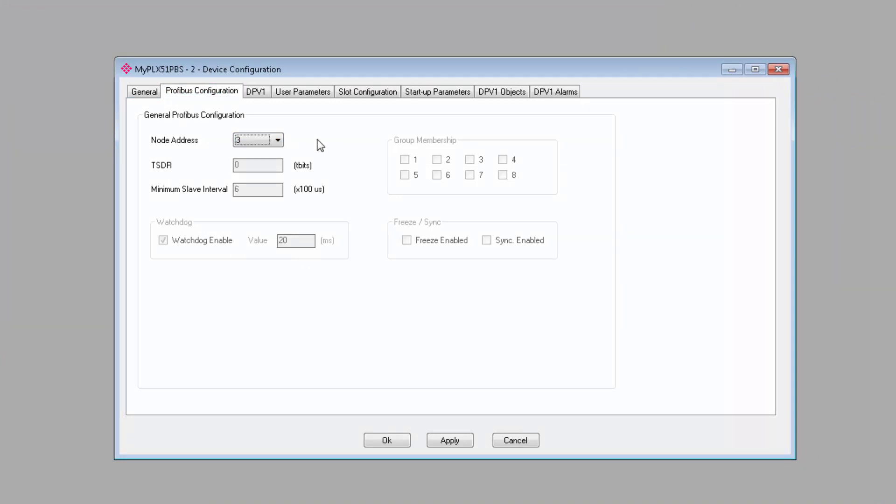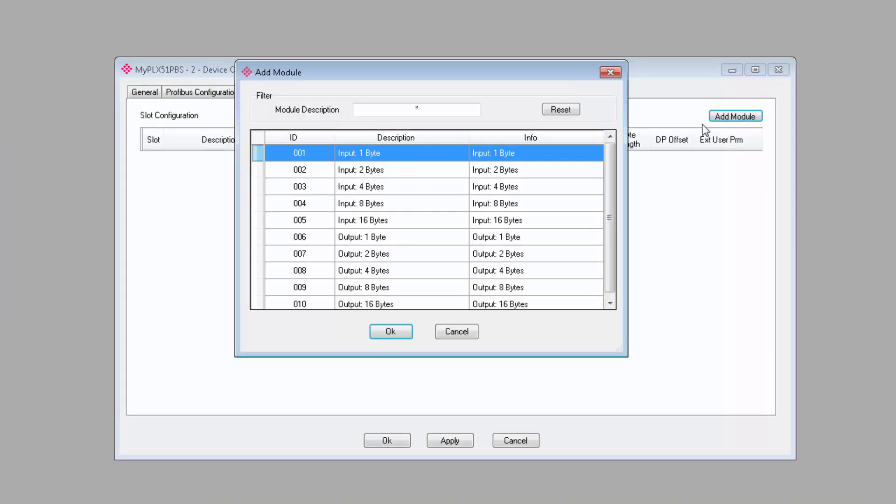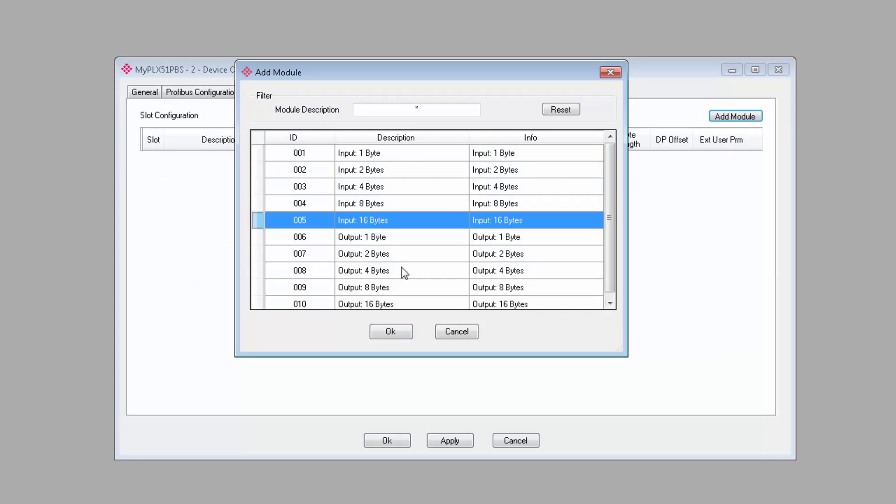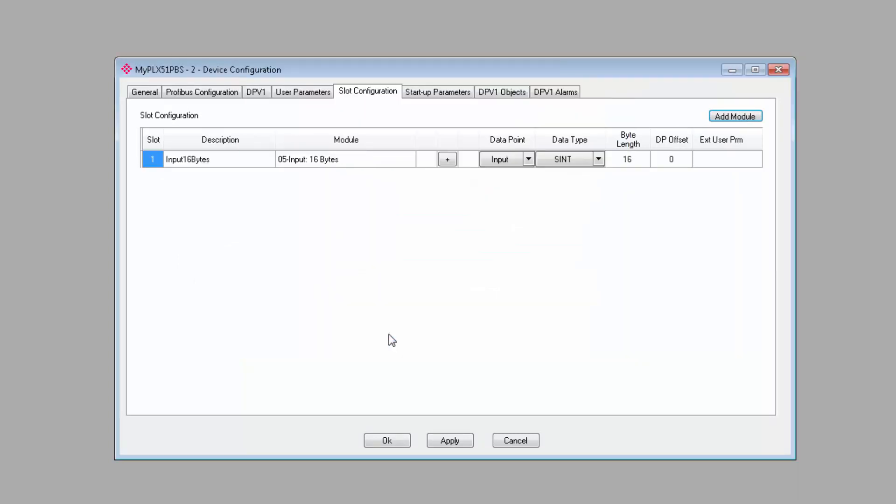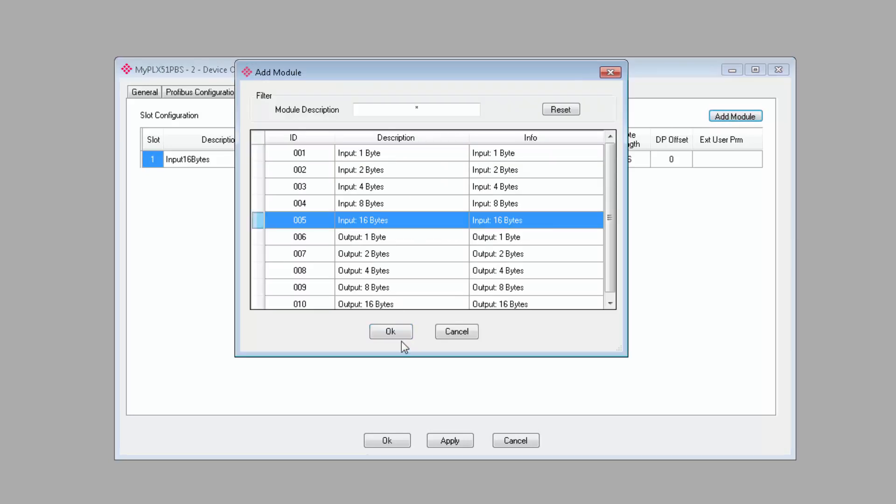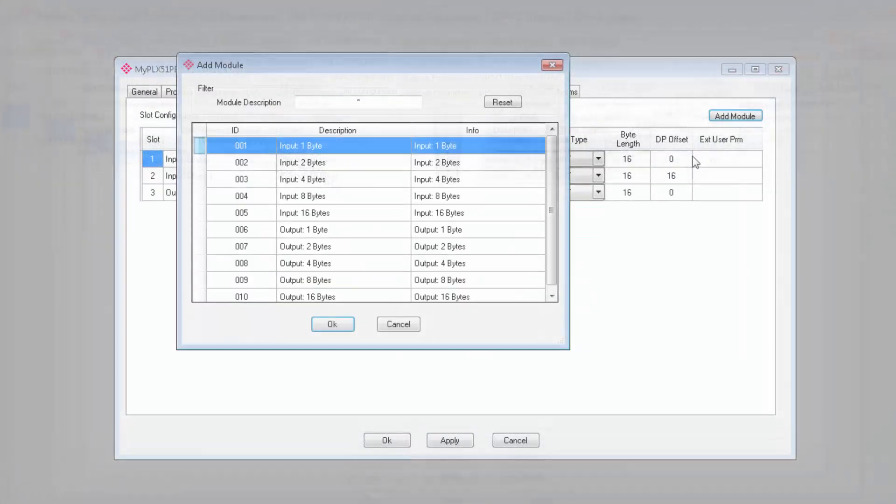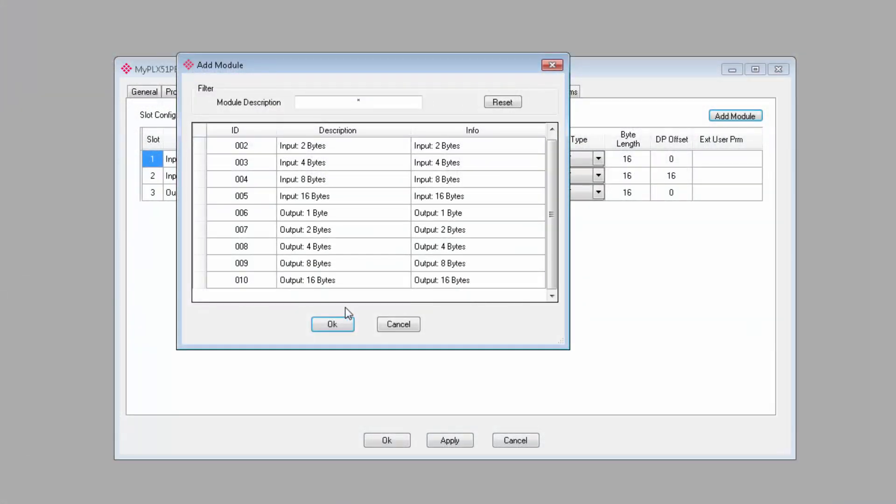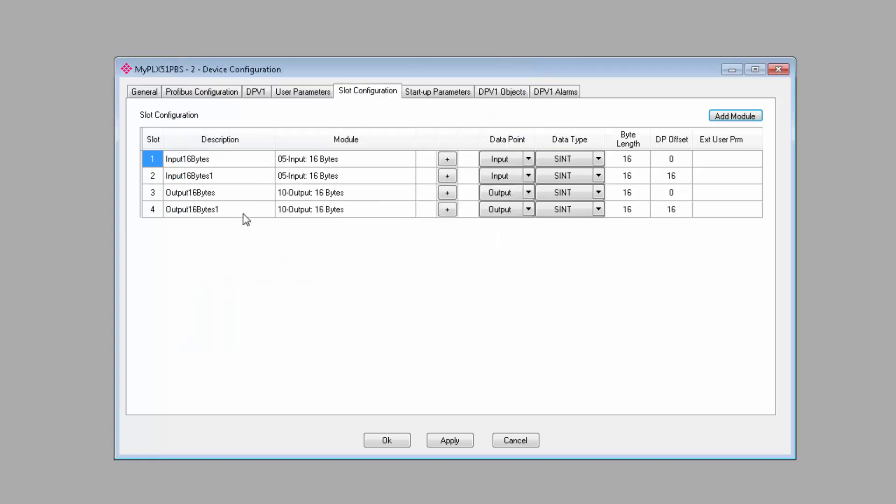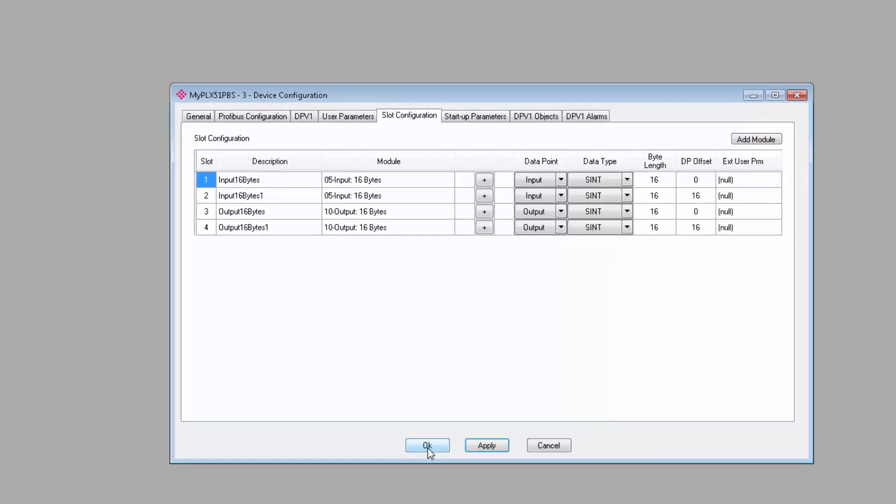On the slot configuration tab, we'll bring in 32 bytes of input and 32 bytes of output. And this will require me to add two 16-byte inputs and two 16-byte outputs. These are single integers by default. If you need a different data type, you can change it here. When you're done, you can click Apply and close this window.